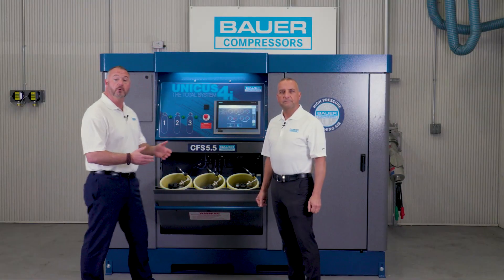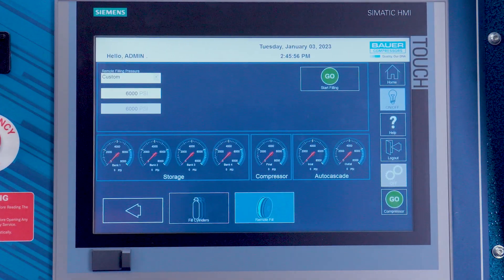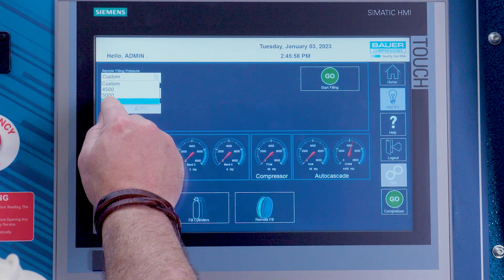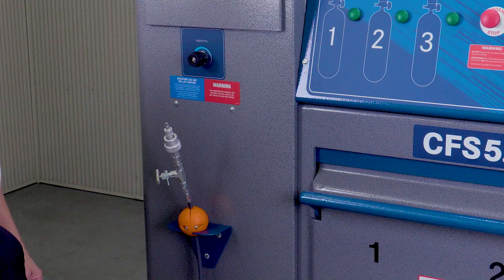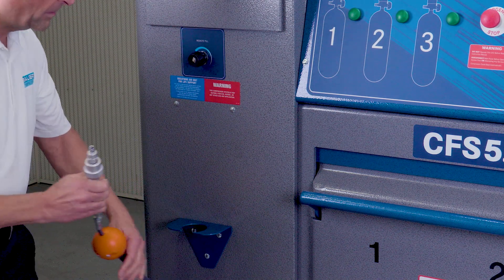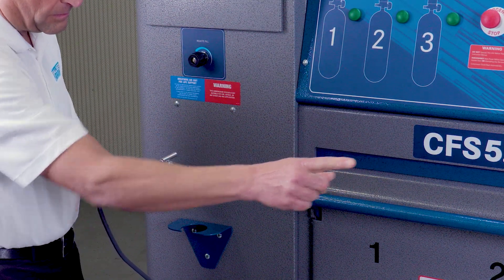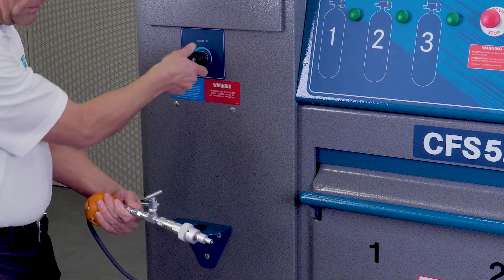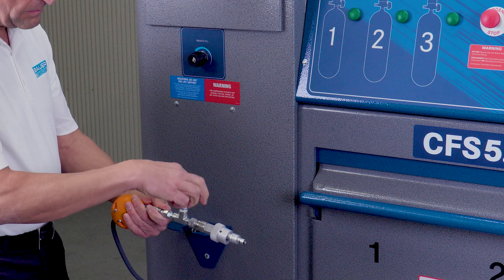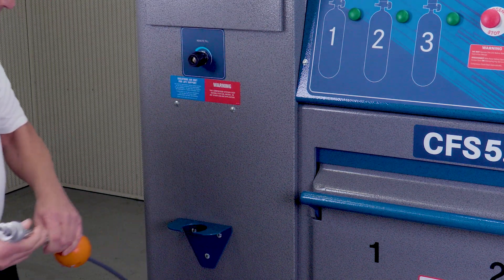Let's discuss the remote fill option. You first need to touch the remote fill icon on the touchscreen, then choose the remote fill pressure and hit the go start filling icon on the HMI touchscreen. Once it achieves the selected pressure, it will go into standby mode — it doesn't turn off. Before disconnecting the hose, the compressor must be turned off. After the unit is turned off, you need to bleed the excess air from the hose before disconnecting it from the fill station or onboard cascade storage cylinder.